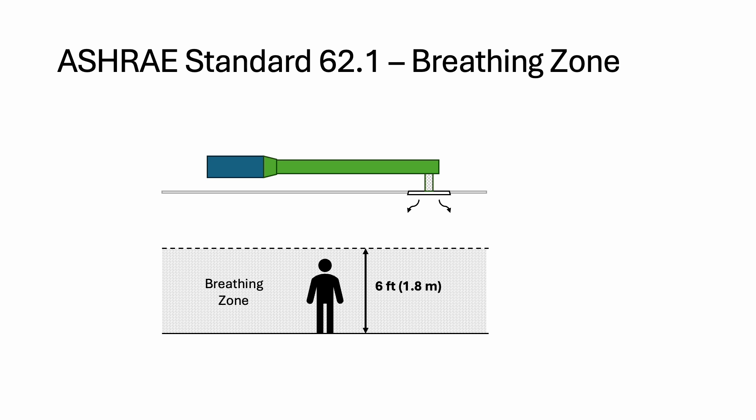Obviously, the velocity is not reduced immediately — there are two steps to this process. First, the diffuser must reduce the air velocity from 1500 to 500 feet per minute. This is done by selecting the right diffuser size.